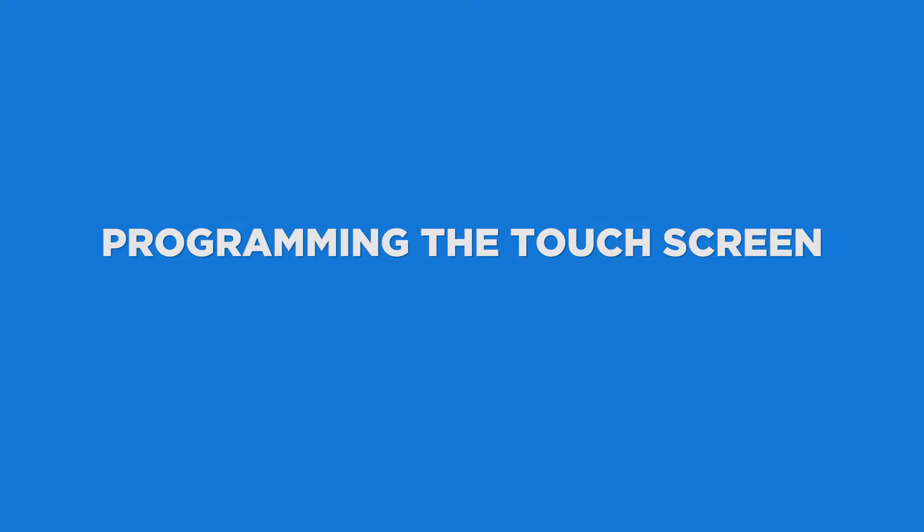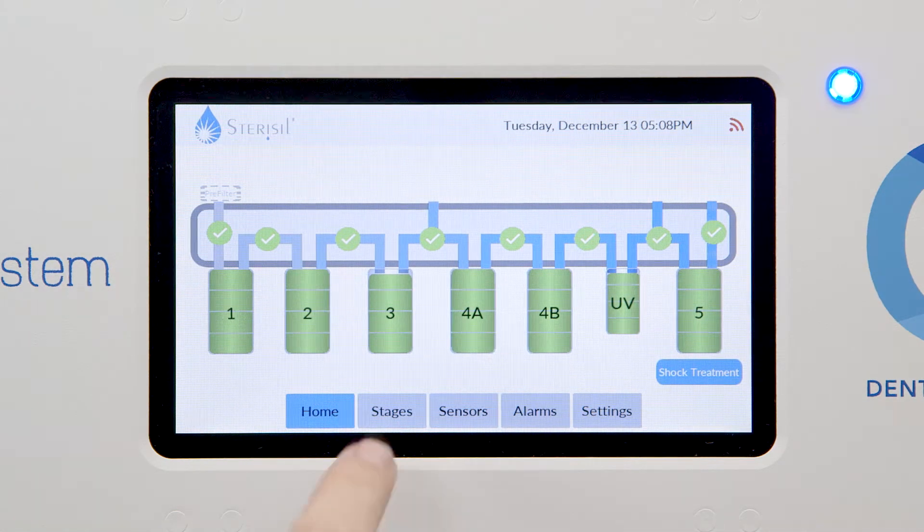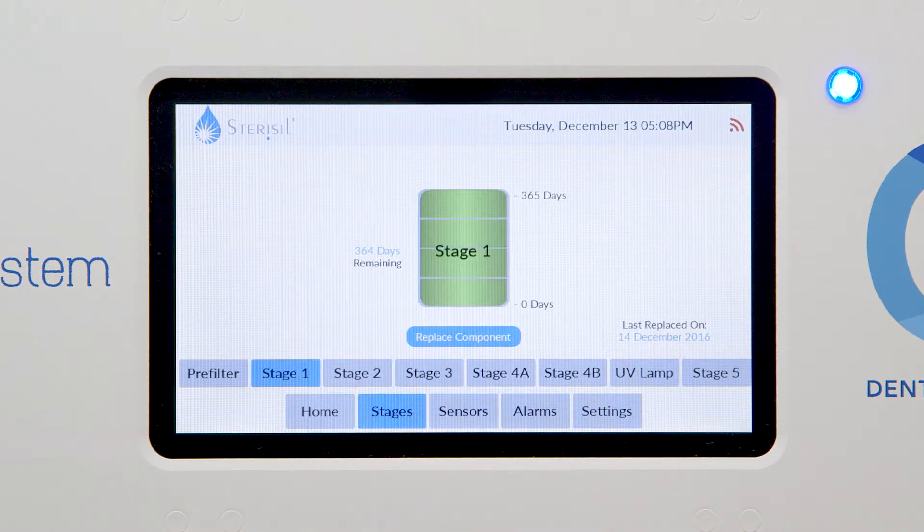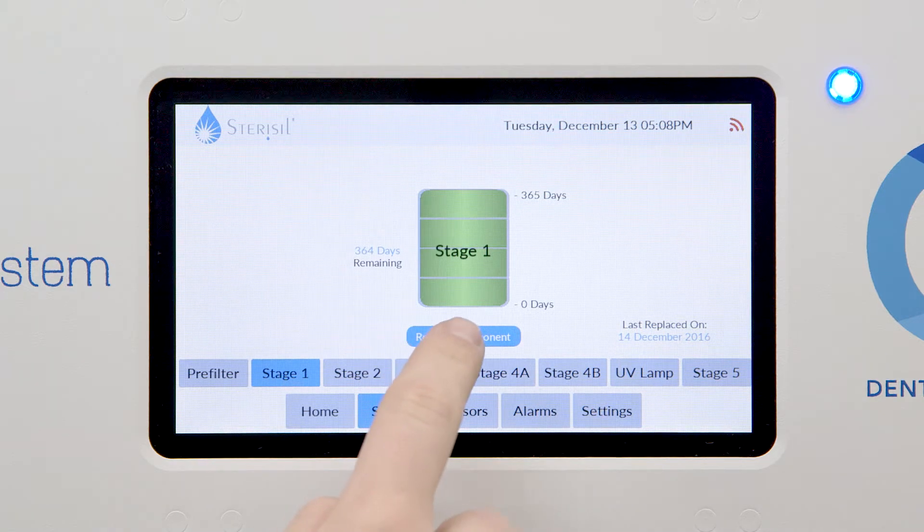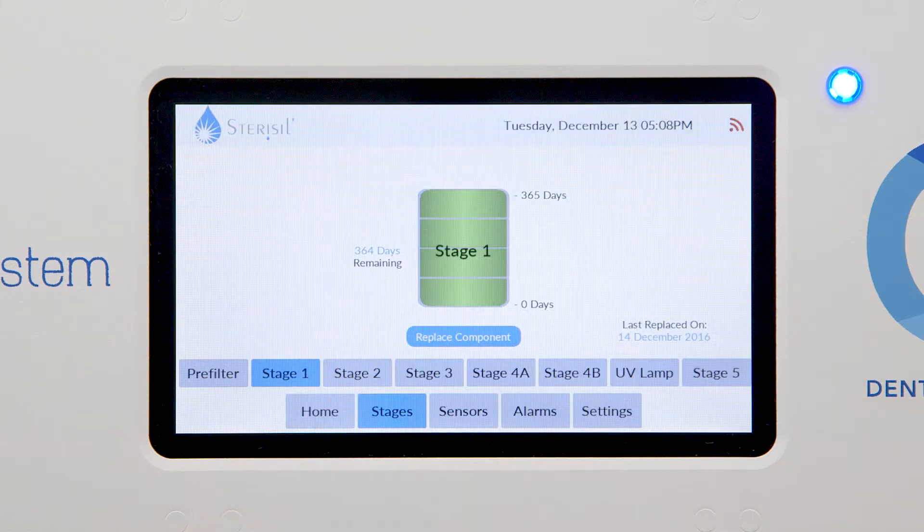Programming the touch screen. Start by bringing up the details view by touching either the desired stage number from the home screen or select the stages tab from the bottom row. Stage one's lifespan is for 364 days. If the counter is not reading 364 days, you'll select replace component. Select stage one from the drop down menu and hit replace.